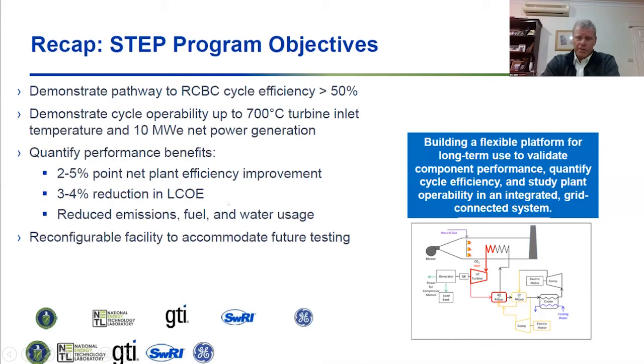One particular supercritical CO2 turbine program you will probably be aware of is the STEP program in the US, a $122 million project — the Supercritical Transformational Electric Power program. Its aim is to demonstrate the RCBC cycle at efficiencies greater than 50% with a turbine inlet temperature of 700 degrees Celsius. It's a 10 megawatt net development, meant to be a flexible platform for long-term component performance development.